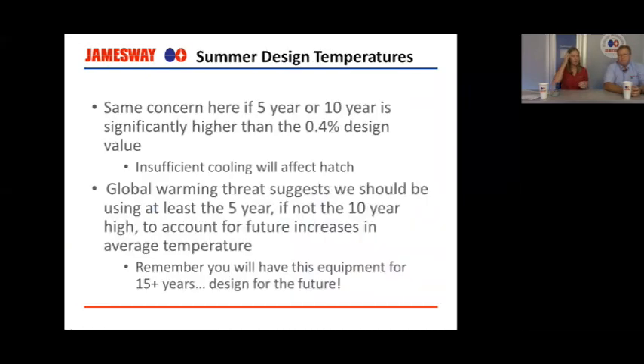So then if we're looking at summer design temperatures, we have the same concern here. If your 5 or 10 year design is significantly higher than the 0.4% design value, and this is all coming from ASHRAE data is typically what I use, then you're gonna end up having insufficient cooling.